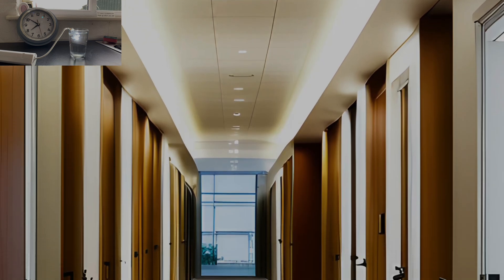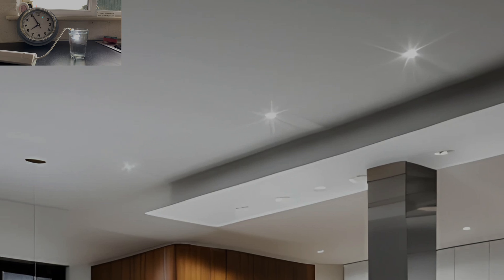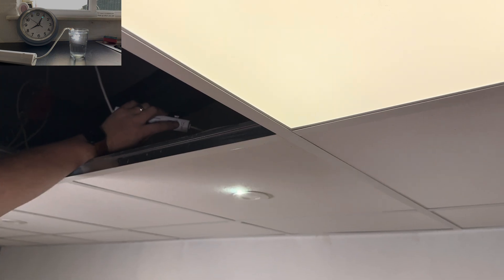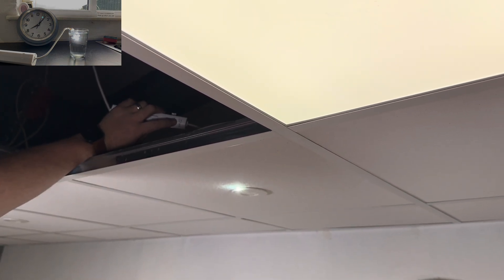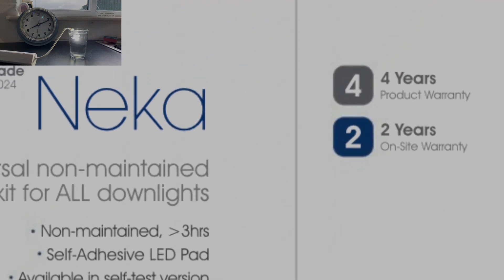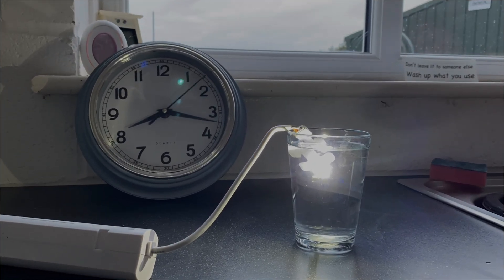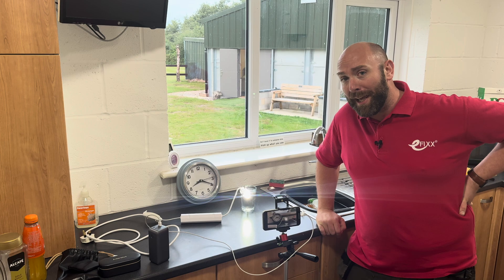What I think is great about this is those retrofit opportunities. Imagine multiple occupancy properties or rental locations where you may be required to install emergency lighting to illuminate escape routes — this is a really unobtrusive way to satisfy those escape route legislations. They can be tested either by pressing the test button or by isolating the supply. This non-maintained unit will operate for the 3 hours required and comes with an impressive 4 year product warranty. And can it survive an hour in a cup of water? You bet it can.